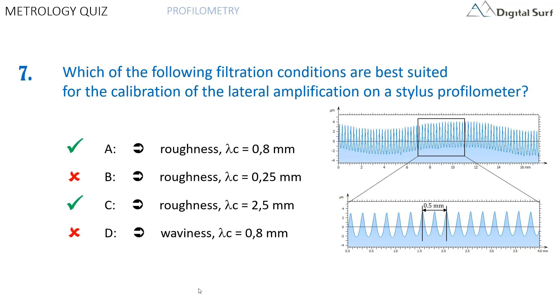The correct answers are A, lambda C equals 0.8 millimeters, and C, lambda C equals 2.5 millimeters, both with a roughness filter. Using a periodic calibration specimen with a known period makes it possible to calibrate the x-axis of a profilometer using a spacing parameter such as RSM. A roughness filter with a cutoff equal to or larger than 0.8 millimeters will ensure that the waviness is removed and the periodical pattern is not affected by the filter. With a shorter cutoff, the periodic features will start to be affected by the filter and the period may be altered. A waviness filter will only retain the large modulation and will remove almost totally the periodical pattern of interest, so the calibration cannot be done.